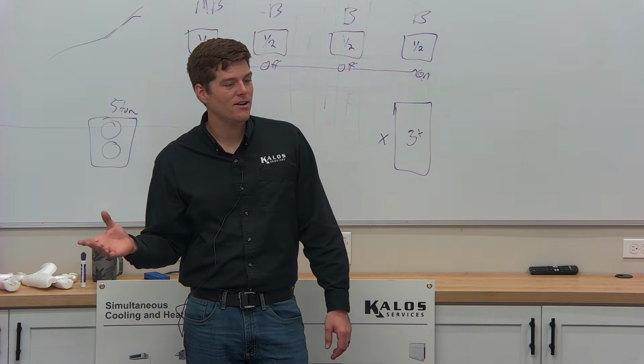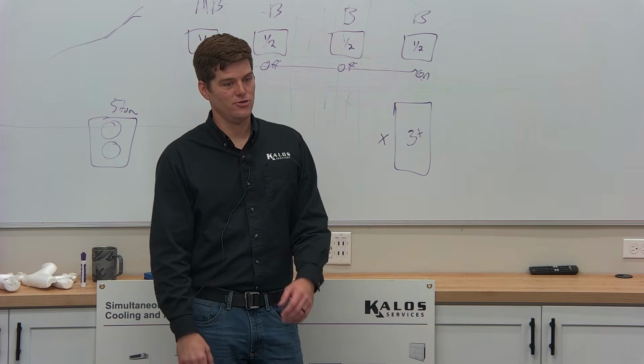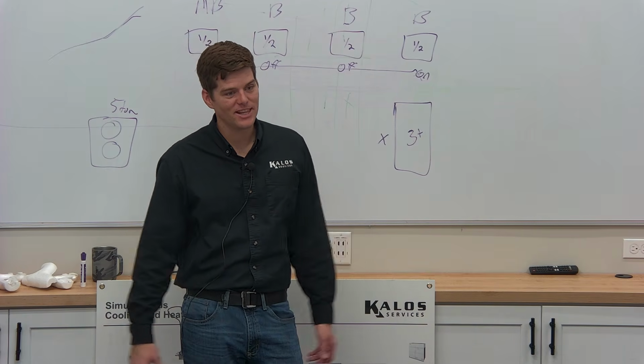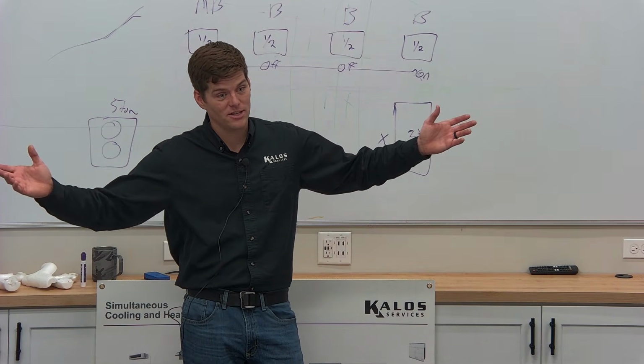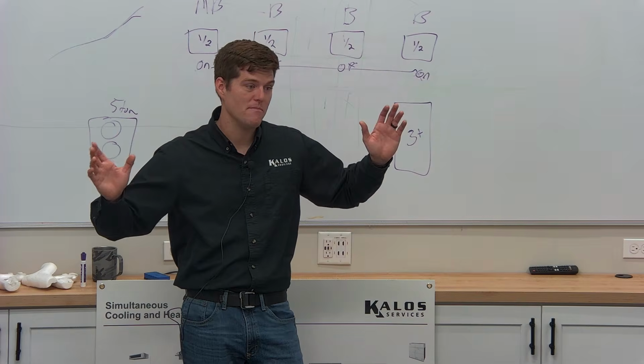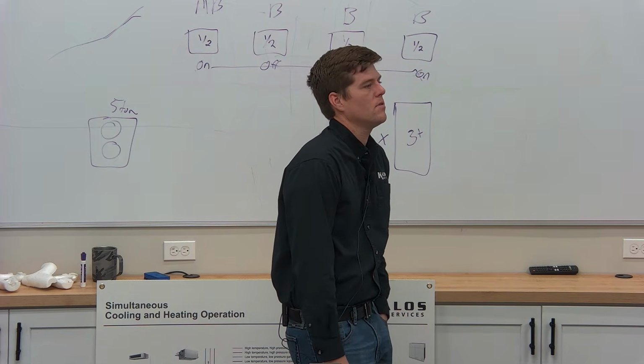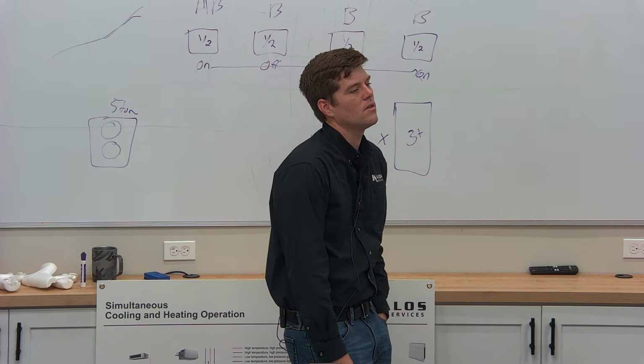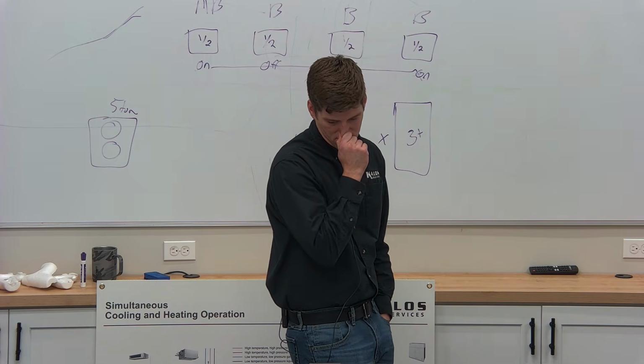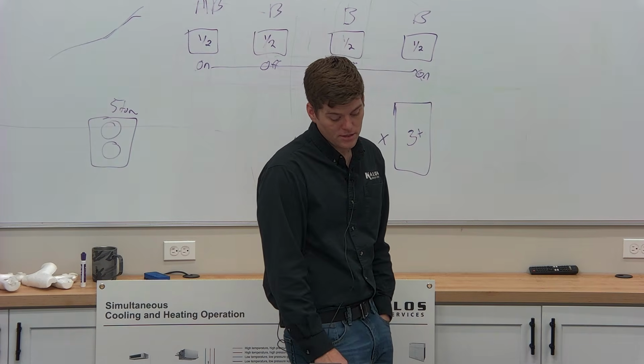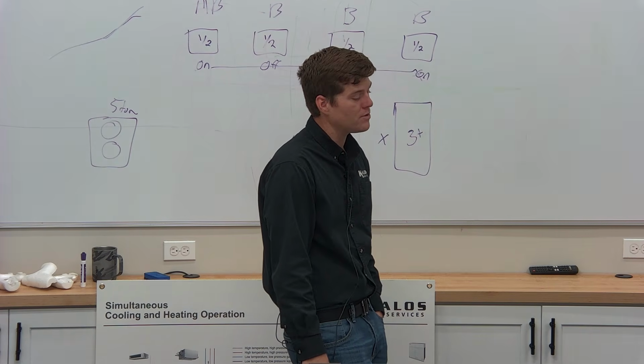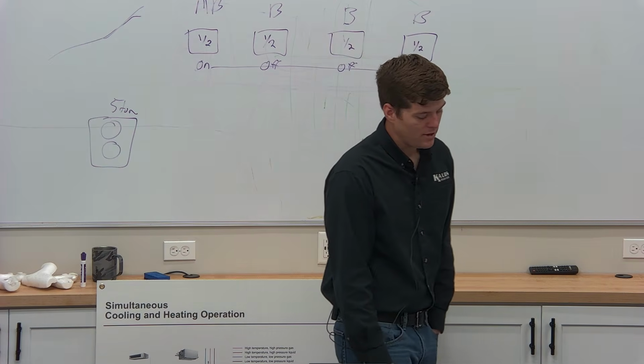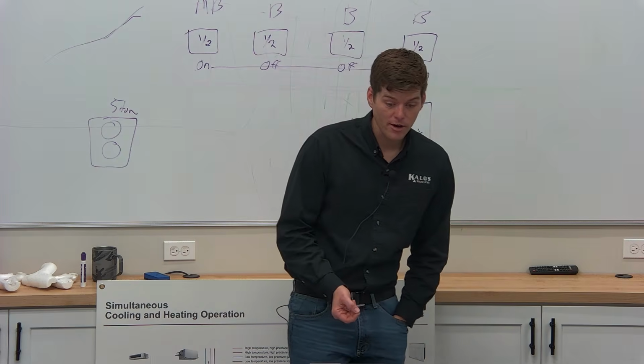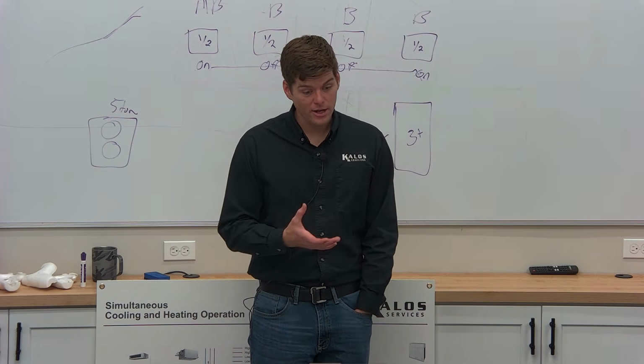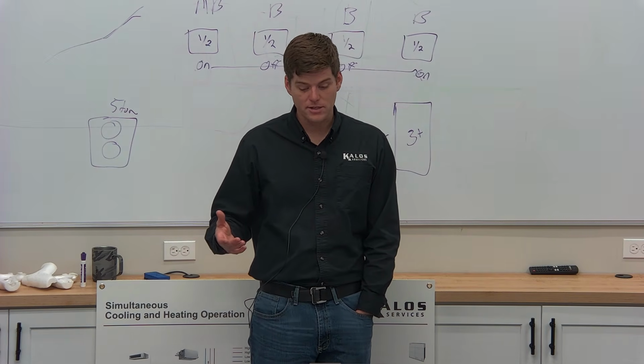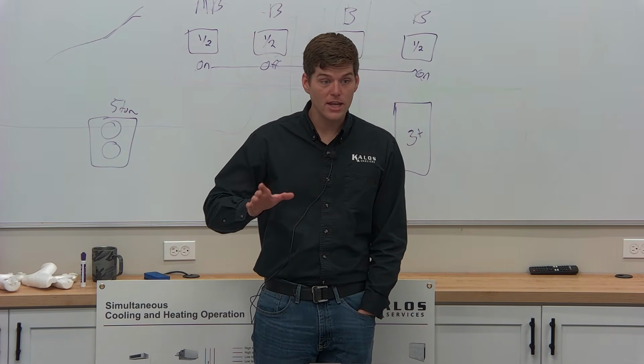And why does that matter? Because we get into that system that has 200 pounds. And it's an assisted living facility. And all the copper is run in hard ceilings. And to access the indoor units is a nightmare. How do you feel about the people that say your torque rating changes based on if you use Nylog or not? Well, it's a good point. The same thing comes when you lubricate the flare itself. A good proper flare that is done using a flaring gauge, deburring with all the right practices, will never need Nylog.